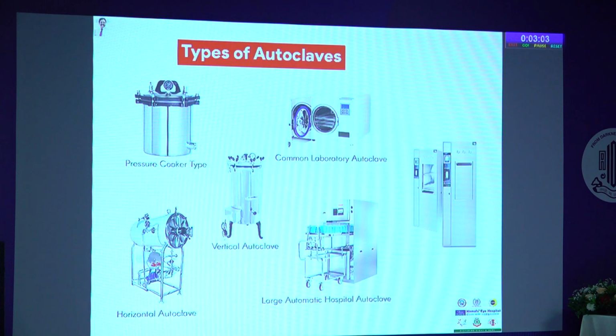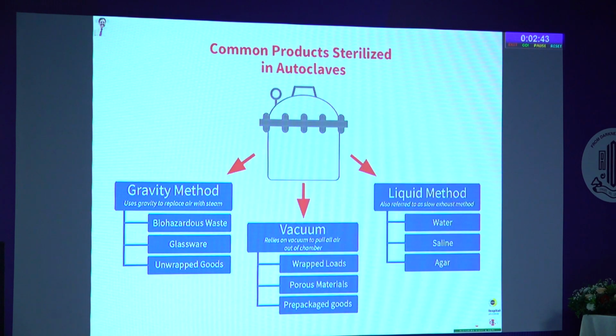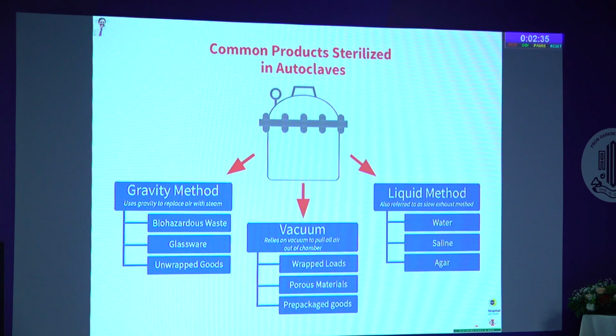So these are the types of autoclave, and most of the practitioners still use the pressure cooker autoclave and vertical autoclave, and most of the accredited hospitals have gone to horizontal autoclave, and large hospitals have the automatic hospital autoclaves. So basically there are various methods, and it depends on the products that are sterilized. The gravity method is basically a lab type autoclave used to autoclave the biohazardous waste. This is a legal requirement to autoclave the biohazardous waste.